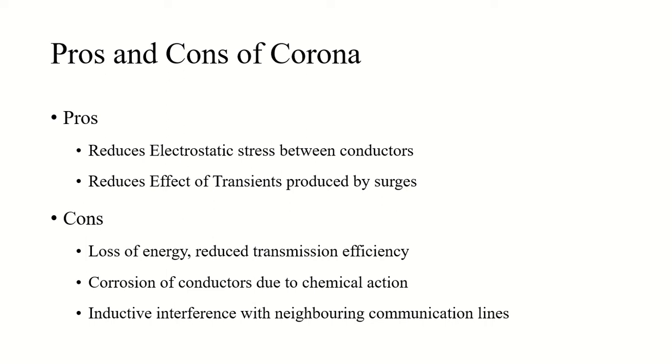Remember earlier we saw how ionization triggers the corona formation, and because of this ionization ozone will be produced, and it will surround my conductors, and because of this ozone you will see corrosion in my conductors. So the life of the conductors is affected.